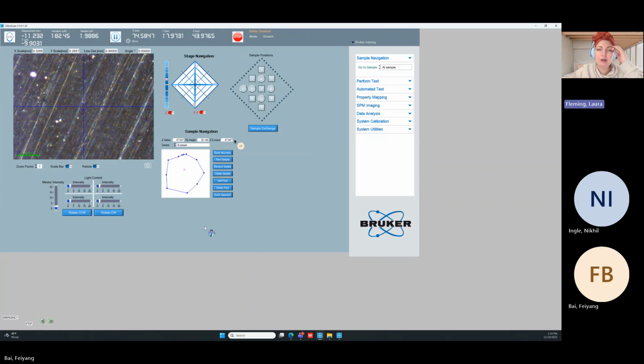So what we did is we added a quick approach, where the quick approach does not have a test attached to it. The quick approach's only job is to get the tip into contact with the sample once to make sure that it has a last contact point so that future tests can be faster. So we did not perform a load function. All we did was a quick approach to update that Z contact point here. So now we will have to go back and do the scratch.